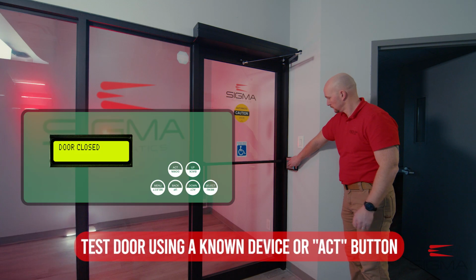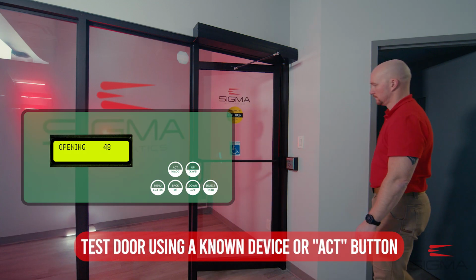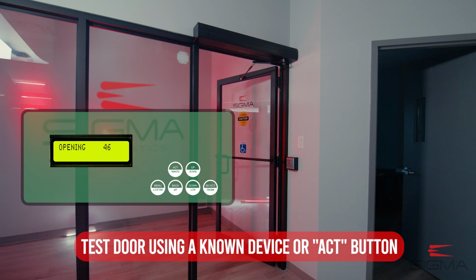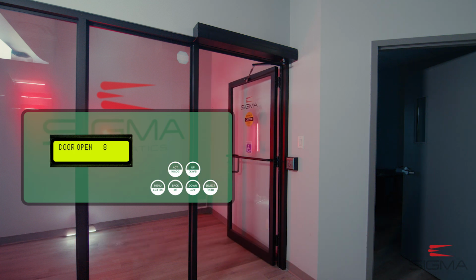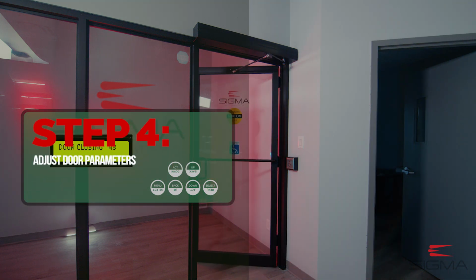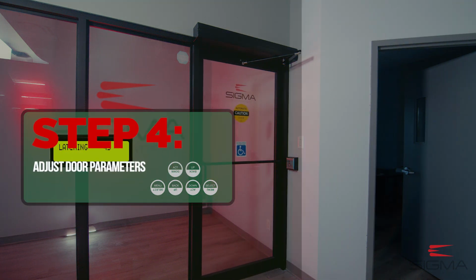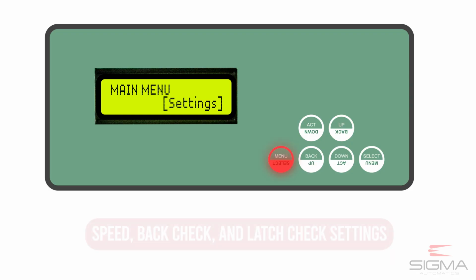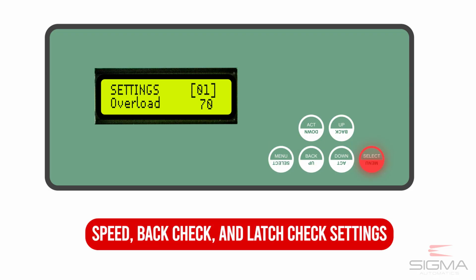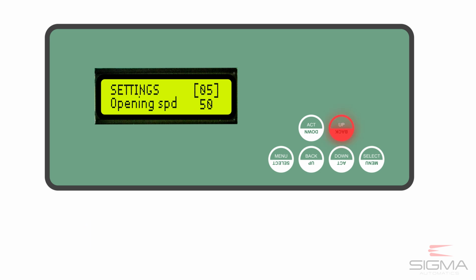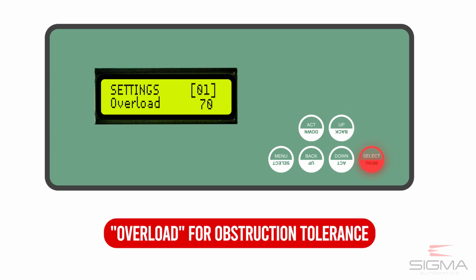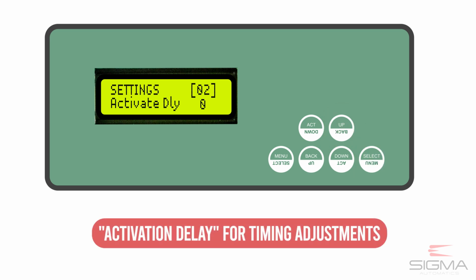At this point, you can test the door by activating it with a known device or by pressing the Act button on the controller. Our factory defaults comply with ANSI 156.19 standards for low-energy operators, but adjustments can be made if necessary. To fine-tune the door's performance, you can adjust parameters such as door speed, back check, and latch check through the menu. Other key settings include the overload parameter, which sets the tolerance for obstructions, and the activation delay, which adjusts the time between the strike trigger and the door's movement.